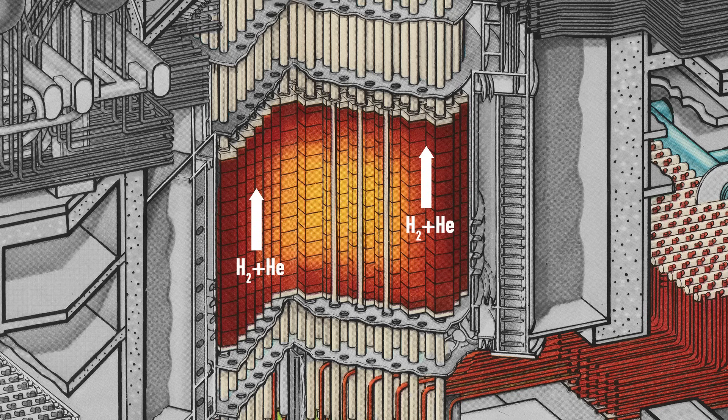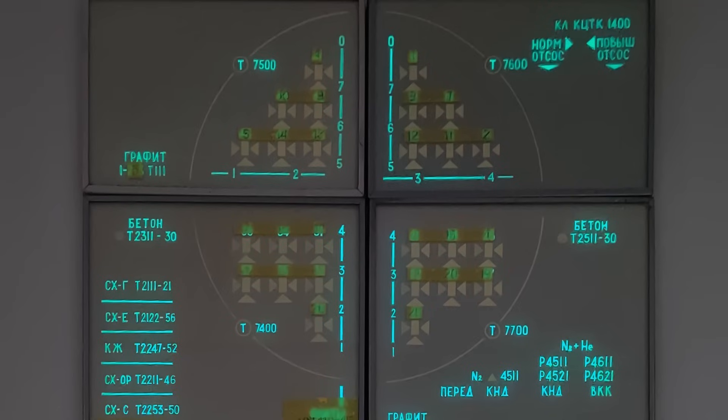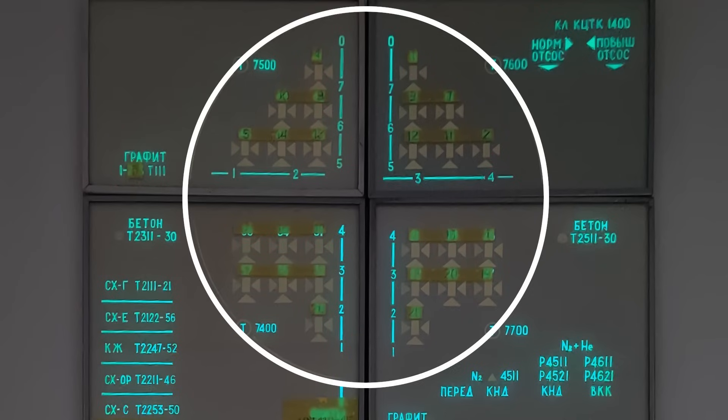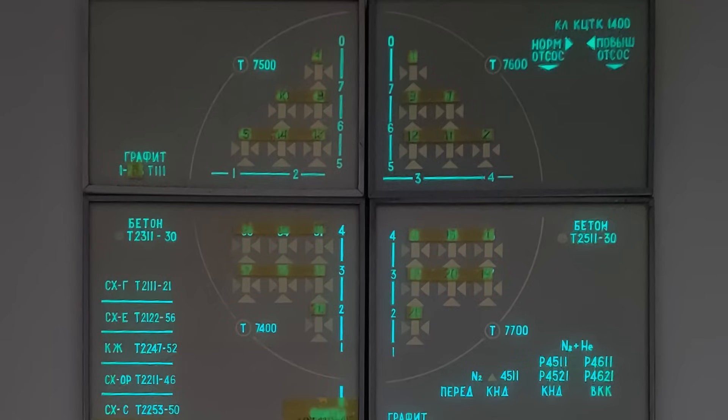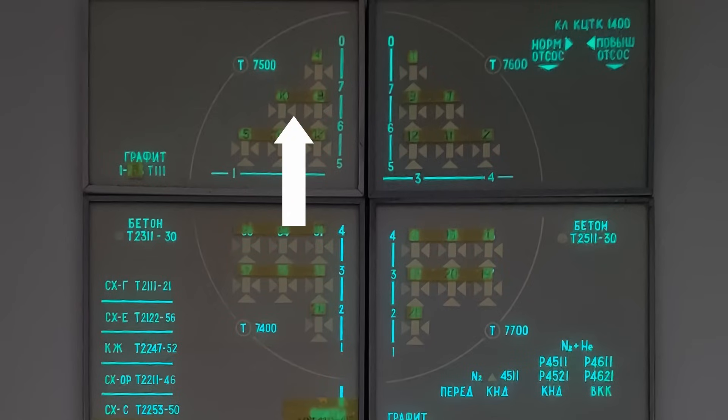And here comes a trick. If we imagine that some channel begins to leak, this dry gas picks up moisture. And inside the reactor there are over 2000 detectors constantly monitoring that. Well, have 2000 indicators is a little bit overkill, so they are grouped in 26 zones, you can see right here. If the leak is found, the operator increases gas flow to dry this area out. And the stages of this pumping and intensity of it will be indicated by changes in triangles on this display.